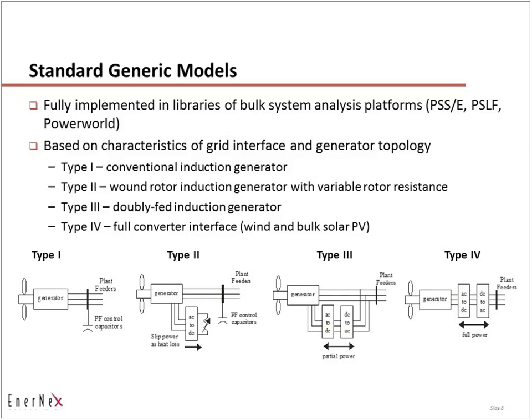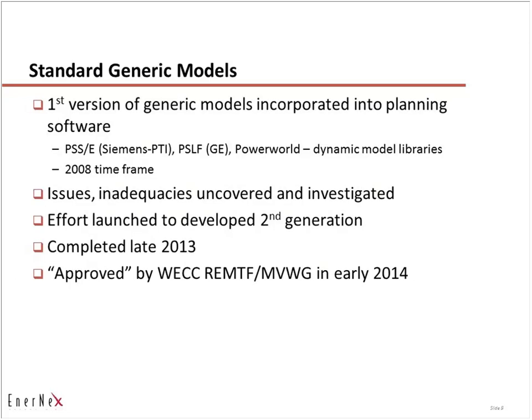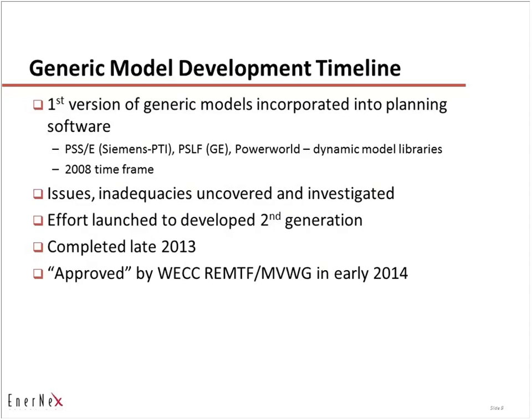As bulk solar came on, it was recognized that the Type IV wind turbine topology — which uses a full converter interface where the electrical machine is completely isolated from the grid through the power converter — would be a good basis upon which to build for completely inverter-based technologies. That has been picked up in what has come out of WECC and has really become the standard.